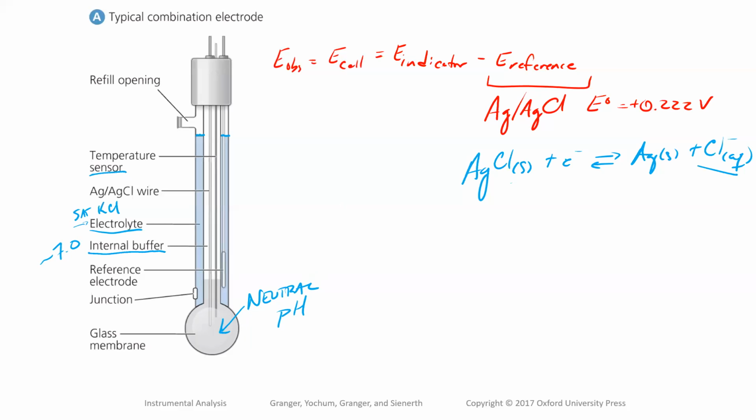This is also why it's very important when you're using pH probes and when you're done using them to put them back in that buffer, right? I don't know if any of you have TA'd for labs that have pH probes, but at the end of the lab, you always put your pH probe back in that little container of solution. The reason is so that if we depleted some H plus, or if we have extra H plus, it can buffer it back out, and we'll get back to that pH of 7 inside our probe.